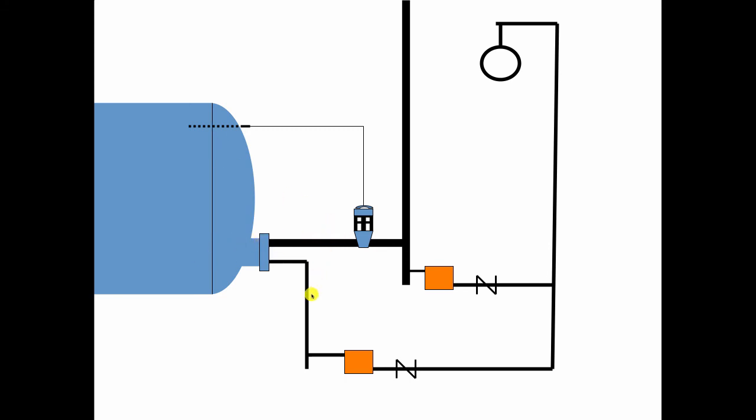And the condensate's going to come out. And as long as that regulator is set properly and it's high enough in pressure we can lift the condensate through the check valve and up. You need one pound of pressure to lift water about two feet. So if this were a ten foot lift into the overhead return we'd need at least five pounds of pressure to get that job done.